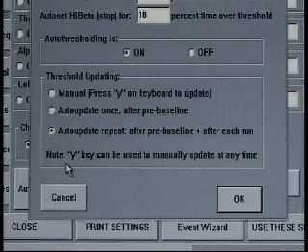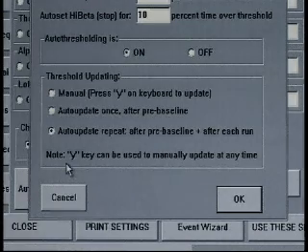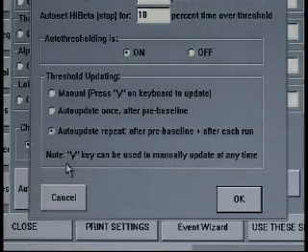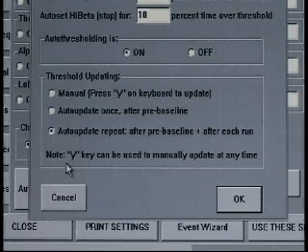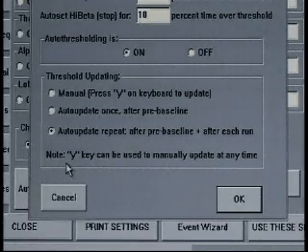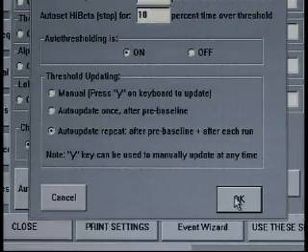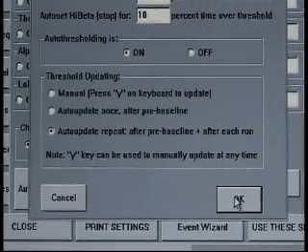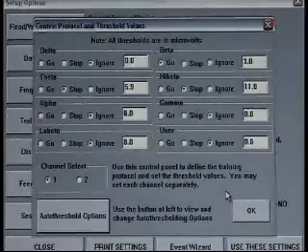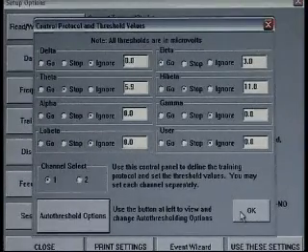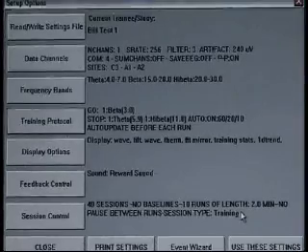Note also that the Y key can always be used to manually update at any time. So if we see the thresholds are a little too easy or a little too hard at any point of the session, we don't need to wait to the next run. We can simply hit the Y key and update them at that moment. Since we've made some changes, we want to remember to always use the OK button to close the window. As we close the window, we go back to the control protocol and threshold value screen. Again, we click OK once more, and we're back to the setup option screen.